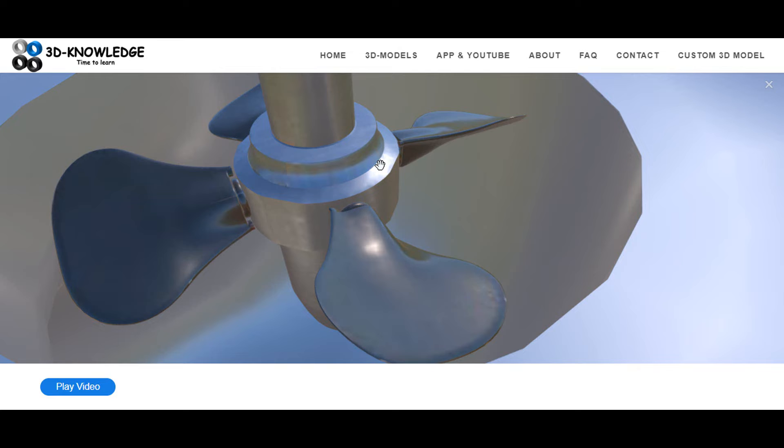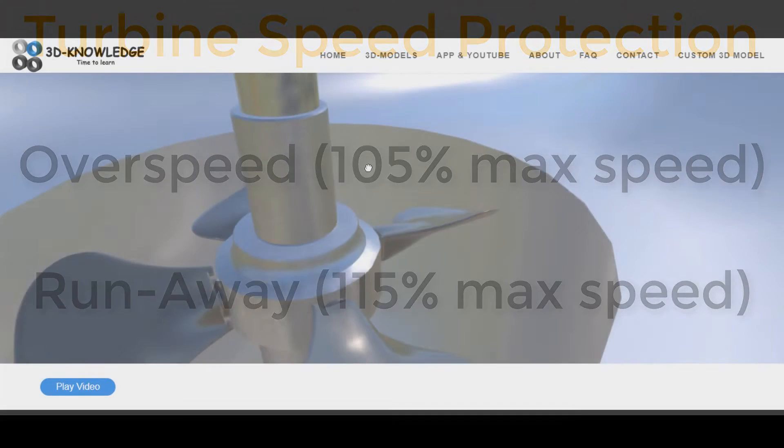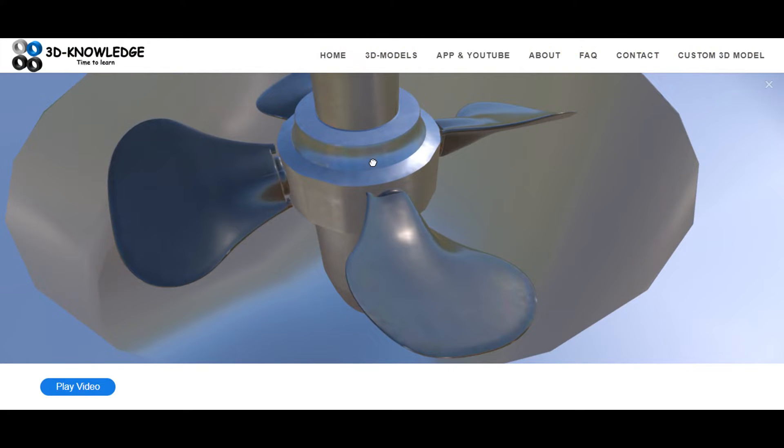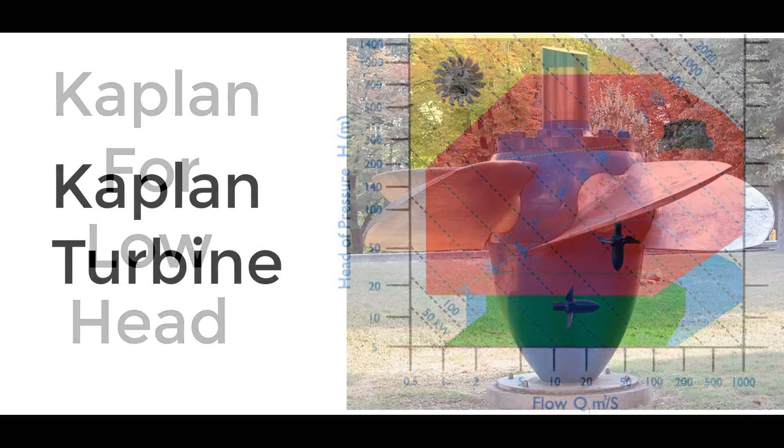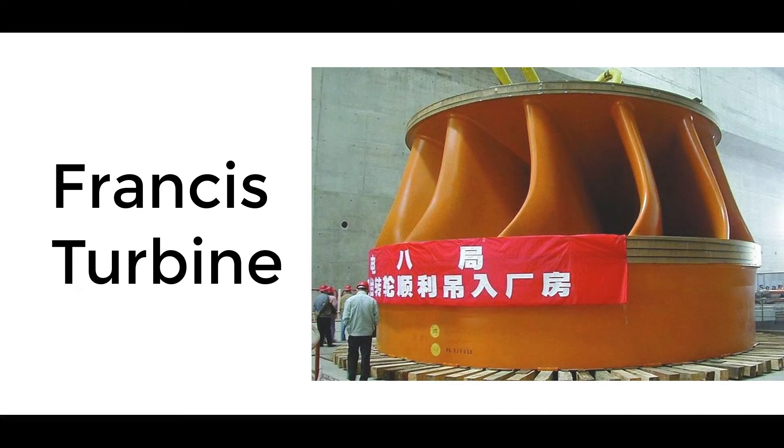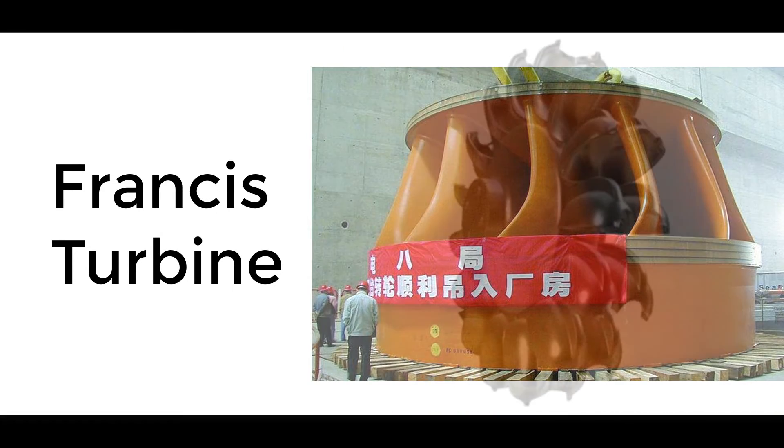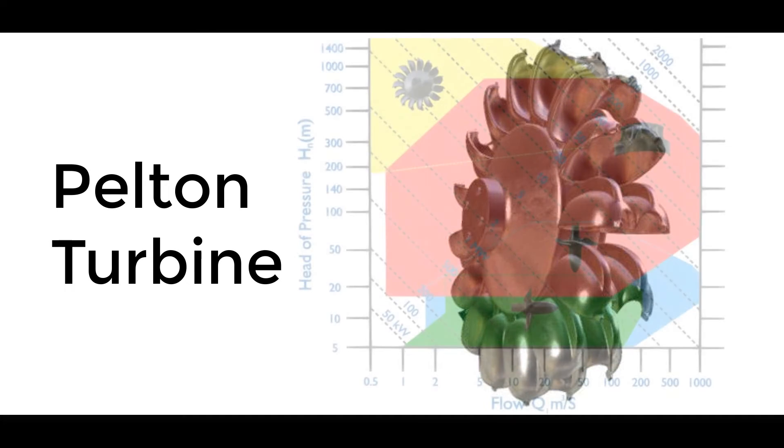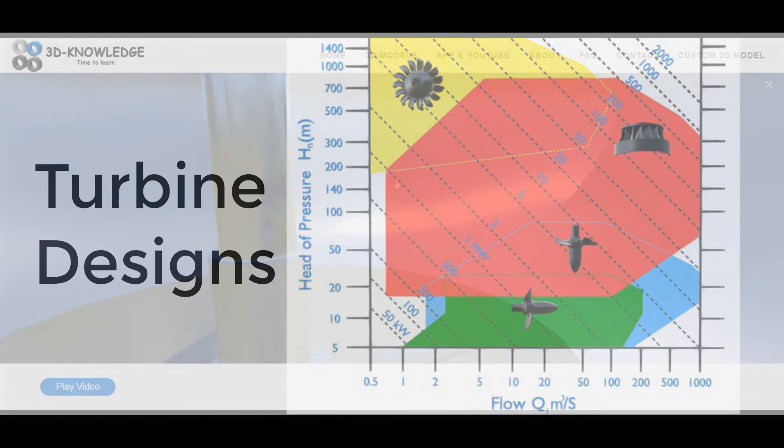If it actually rotates uncontrollably, it will hit an overspeed limit and a runaway limit, and that then sends a signal to the control unit to shut the turbine down. The type of turbine used here, the Kaplan turbine, is chosen because it actually works very well at low heads. That means the difference in elevation between the upper reservoir and the lower reservoir is very small and the Kaplan turbine is ideal. You may even see a horizontal Kaplan turbine or a bulb turbine, maybe Francis turbine but not as likely, and what you won't see is a Pelton turbine. If you want more information about that, just go on my YouTube channel and check one of the other videos where we've explained what each of the turbine types do and why they're selected for each application.